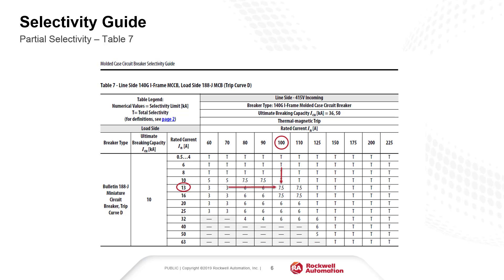This means that if the maximum prospective short circuit current on the load side of the 188J breaker is more than 7.5 kA, it would not be possible to ensure selective coordination — meaning both circuits could trip.